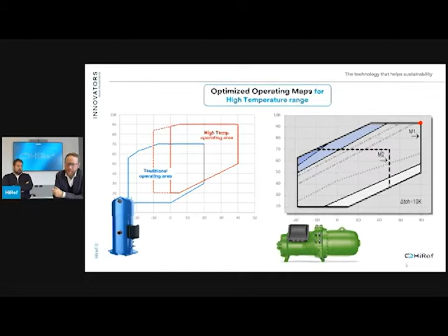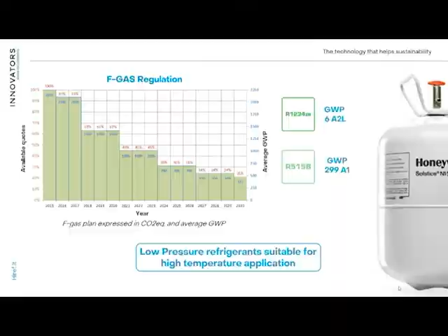This is considering also the application of the new generation of refrigerants that, thanks to the F-gas regulation, give us the possibility to reduce the GWP. We need to use low pressure refrigerant with very low global warming potential, for example 6 for the R1234ze, or 299 for the R515B. So we understood that we need a heat pump, which will increase the temperature level of the waste heat from the data center, making it more suitable for other types of application.